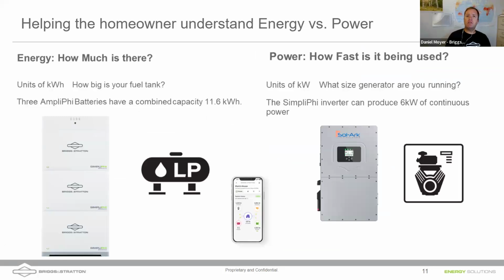A lot of times when we're dealing with generator installers or maybe even homeowners, I think generator installers understand power, right? When we go to look at a home and we're sizing a generator for a home, we look at the square foot of the house. We add 3 VA per square foot. We look at some of the larger home loads, and we look at some of those kitchen circuits, and then we come up with how many watts or how many kilowatts a generator needs to be in order to support that home. Maybe a 22K generator, maybe a 13K generator.